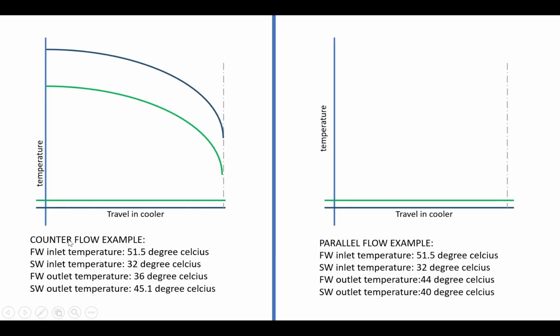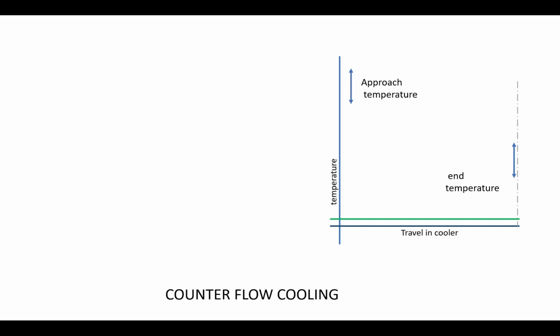Here is one example. Counterflow cooling example. Fresh water inlet temperature is 51.5 degrees Celsius. Seawater inlet temperature is 32 degrees Celsius. Let's introduce the seawater into the system. Seawater temperature will slowly increase: 37 degrees, 39 degrees, 42 degrees.